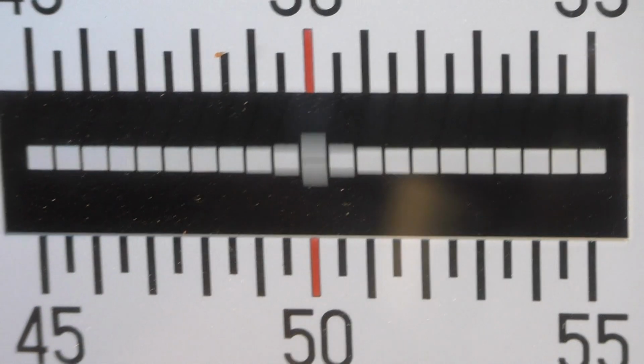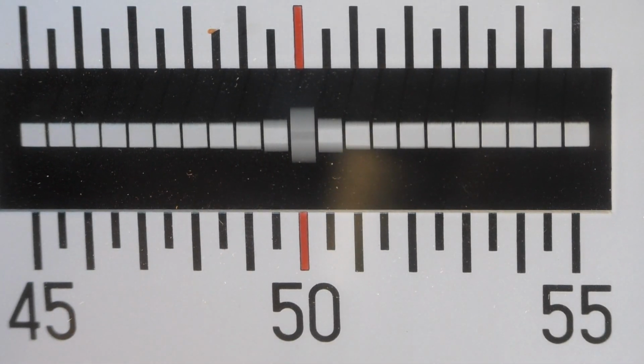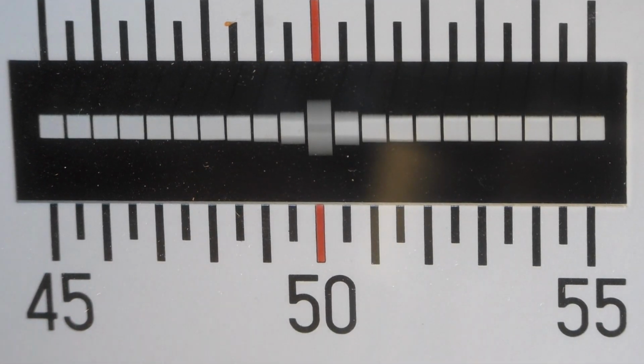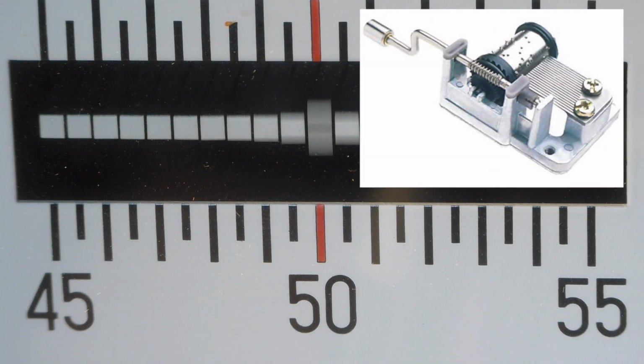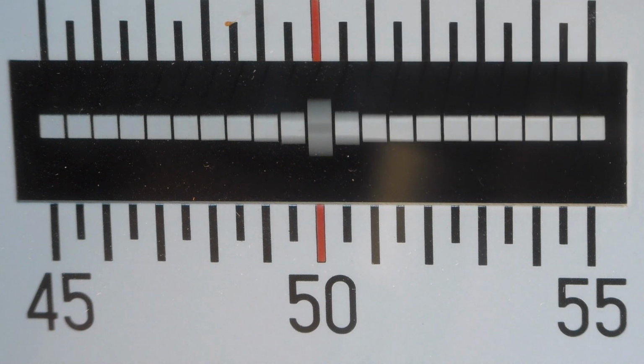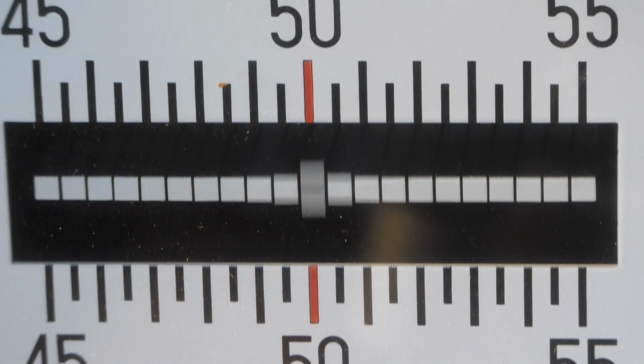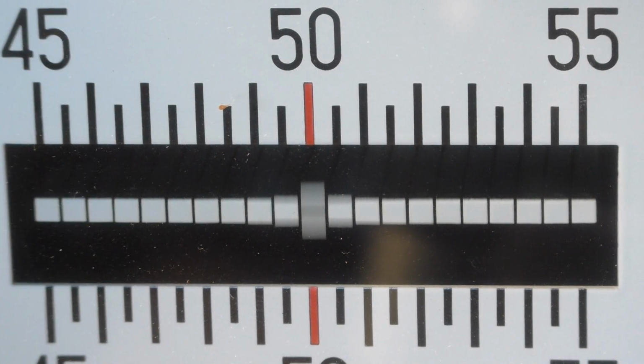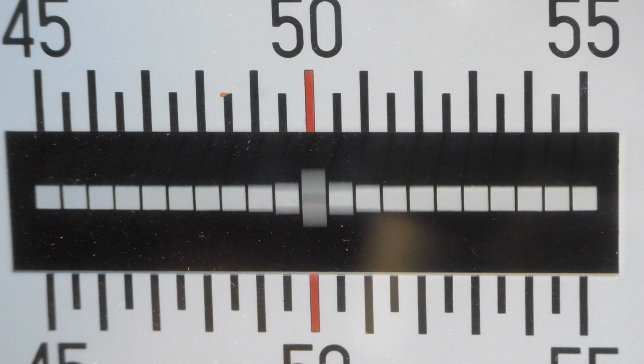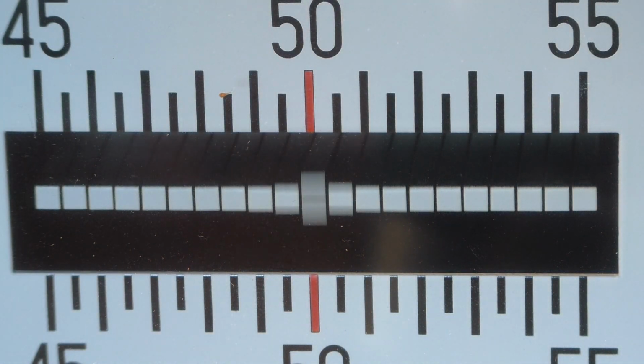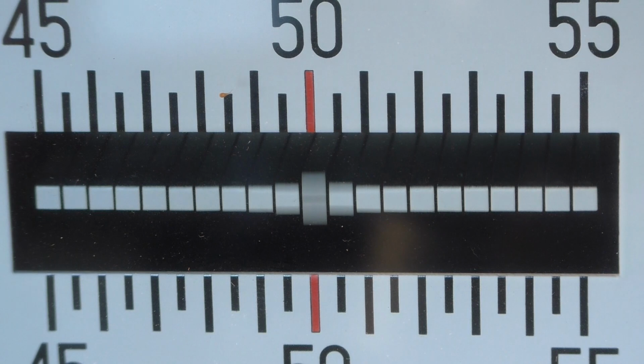This instrument uses reeds, like the musical reeds of those tiny hand crank organs you probably know. And they are exactly tuned to 45 to 55 Hertz, with 50 Hertz in the center, because it's a European model. An American model would have 60 Hertz in the center, and it's used to measure frequencies.